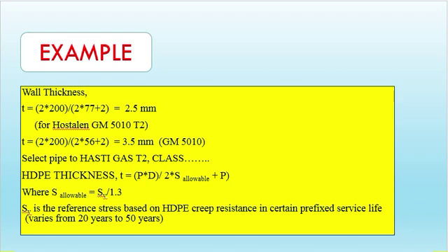For wall thickness selection of Class 2 HDPE pipe, the formula is: T = PD / (2 × S_allowable + P), where S_allowable = SY / 1.3. Wall thickness must also satisfy T ≥ 2.5 mm minimum.